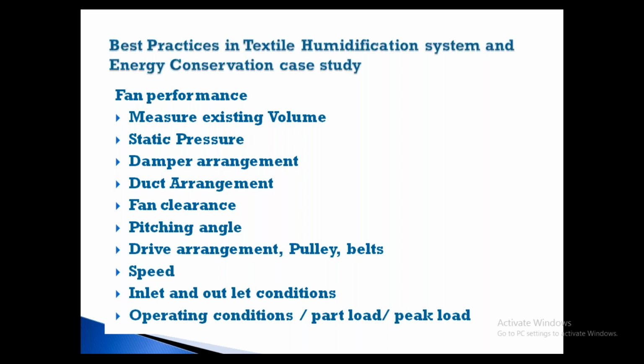So pitch angle is there. Then drive arrangement, pulleys and belts. Of course, some expert on the belts is going to talk, I think. So what are the pulley and belts? If it is a belt drive, what impact is it going to have on your slippage loss and on achieving the designed RPM? So for that drive arrangement, mostly in axial flow fans, it is better if you have a direct drive arrangement. You change the blade angle, with a direct arrangement.